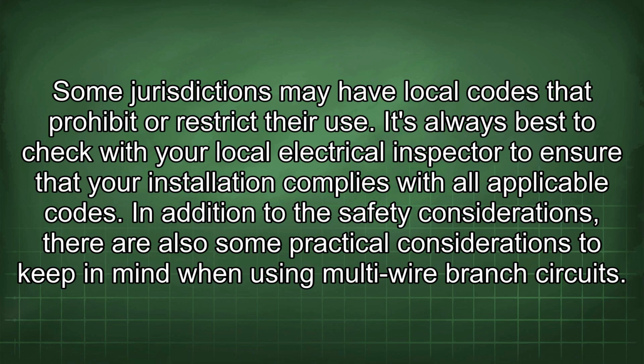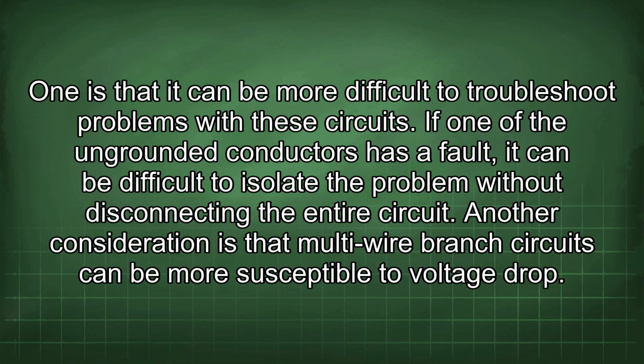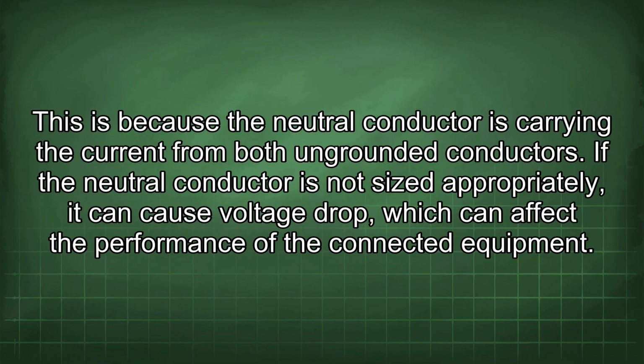In addition to the safety considerations, there are also some practical considerations to keep in mind when using multi-wire branch circuits. One is that it can be more difficult to troubleshoot problems with these circuits. If one of the ungrounded conductors has a fault, it can be difficult to isolate the problem without disconnecting the entire circuit. Another consideration is that multi-wire branch circuits can be more susceptible to voltage drop. This is because the neutral conductor is carrying the current from both ungrounded conductors. If the neutral conductor is not sized appropriately, it can cause voltage drop, which can affect the performance of the connected equipment.